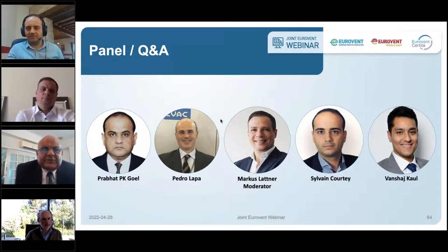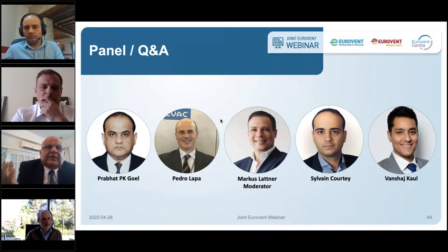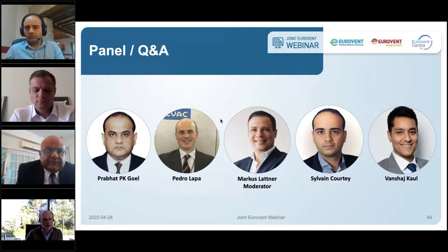it's penny-wise, pound-foolish to install small equipment above the ceiling, which you will rip out in 3 years and do it again, rather than be a good designer, provide these spaces, these footprints, and good equipment installed in a good way. In the Middle East and India it lasts 20 years. I can take you to air handling units in Dubai which are more than 20 years old, and they are still there. You know, double skin units, which came from Europe from very renowned sources, replaced those single skin units probably installed in the 80s, and you would still find them. So my answer to this would be, go by the low air velocity, find the space.